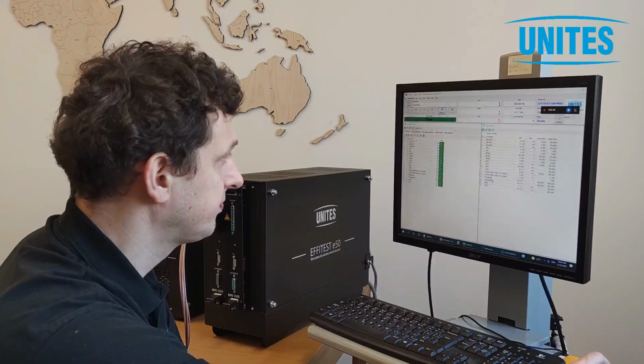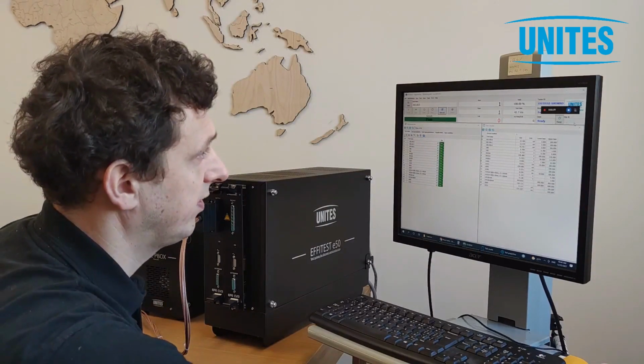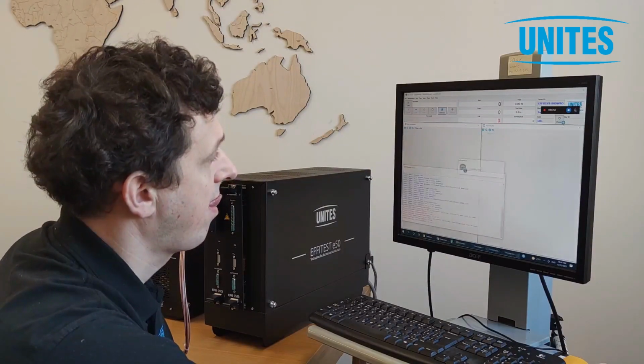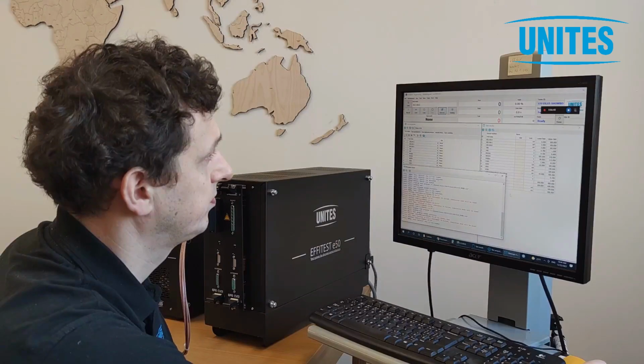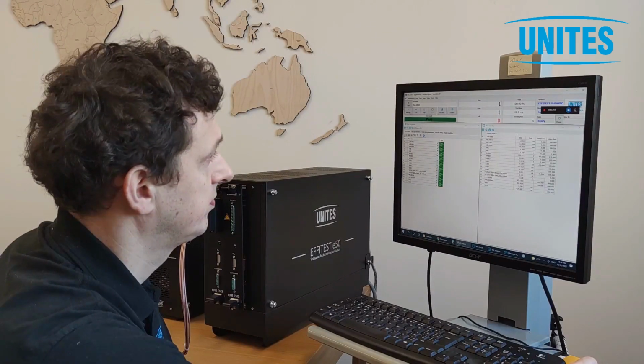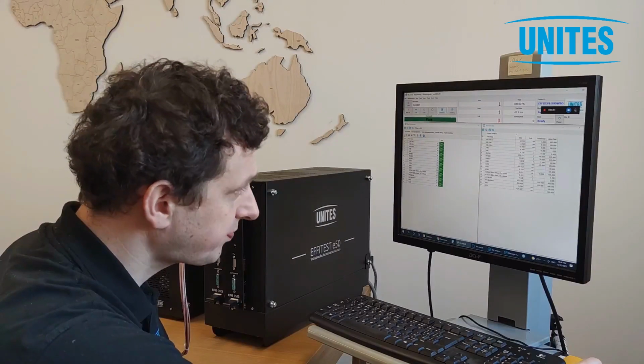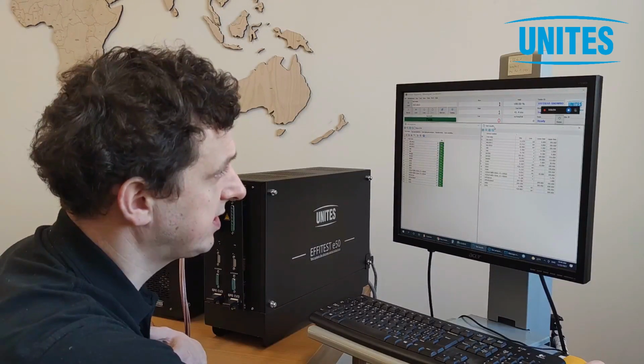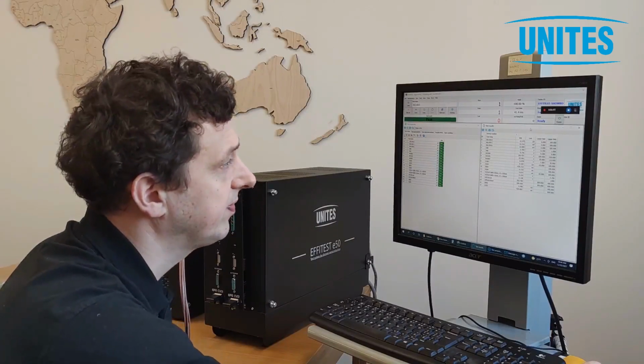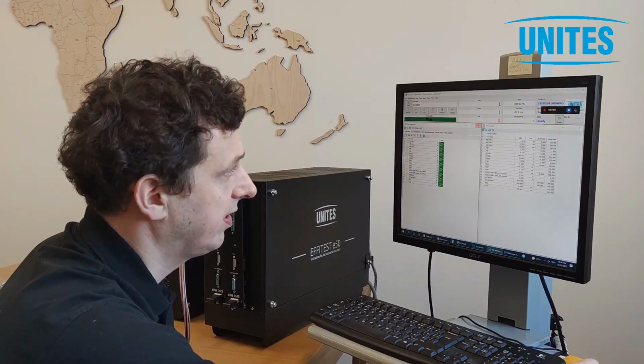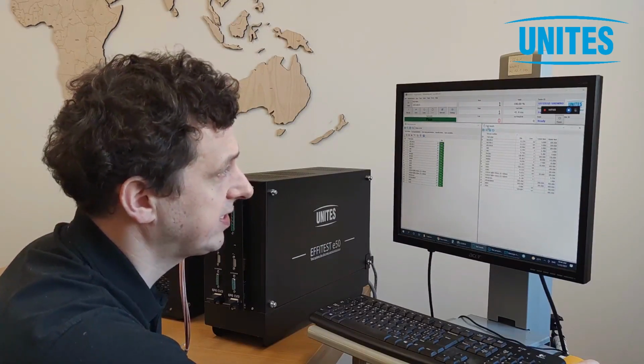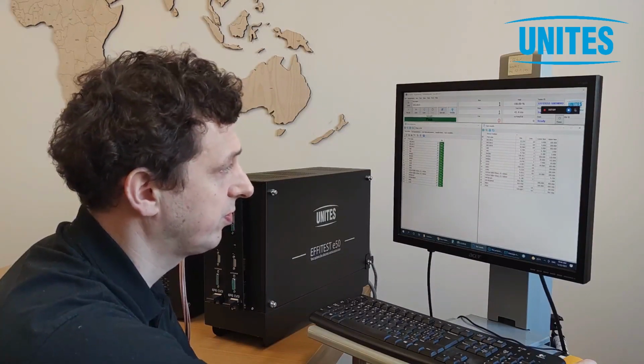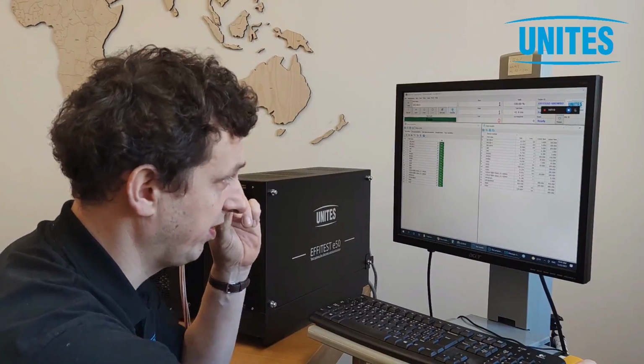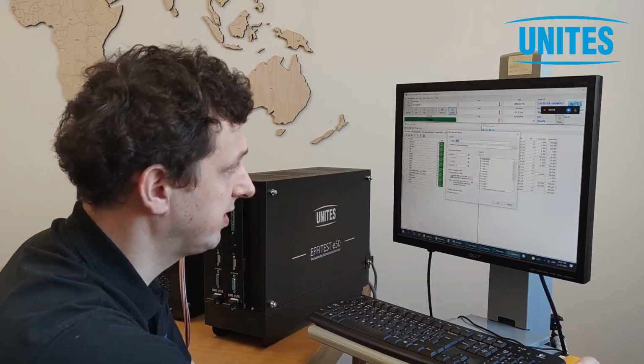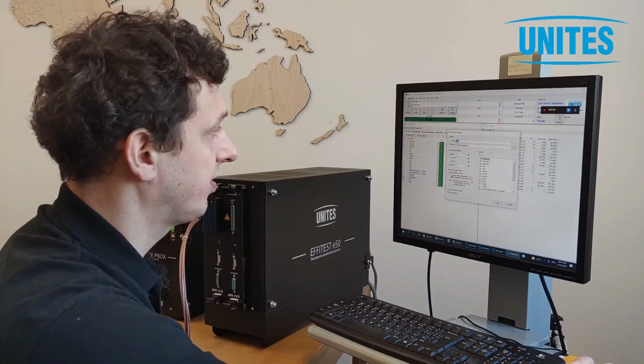Let me close the program and check it again. Switch it on. Again, pass. The problem here is that I can see only the last run of the test system, so the last results. To have more information about the testing, we are using so-called data log, which is automatically launched in the production mode. So if the operator is operating the tester, or if it's on automatic mode, the data log is always there. And locally, we are storing all the measurement data.